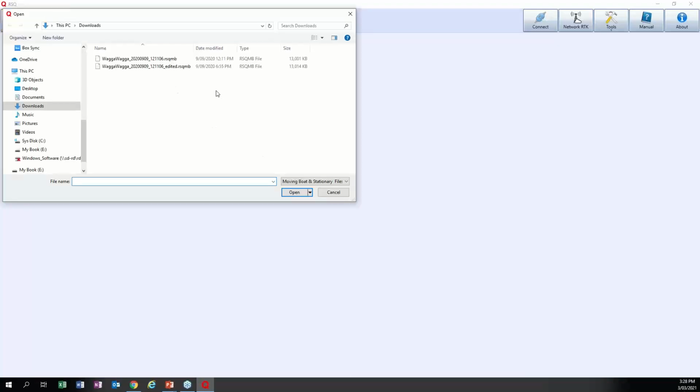So if we open a file, you will see there's two files. One without the edits and then the edited included. So this is very similar to Flow Tracker 2, where at SonTek we tried to keep the original data set as secure as possible. So any changes or edits made to it will be stored in a separate file. This is very good practice for data management and quality assurance. It also indicates or provides the auditor of the data that changes were made to the actual measurement.